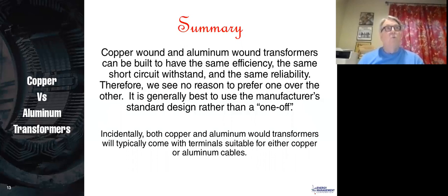Incidentally, we sometimes use copper cables and copper wiring. Sometimes we use aluminum. That doesn't make any difference because whether you have an aluminum wound transformer or a copper wound transformer, either one, the lugs can accommodate copper wire or aluminum wire. And so that really isn't an issue here either. So as a summary, I would say go with the standard and don't be worried too much whether it's got copper or aluminum wiring.